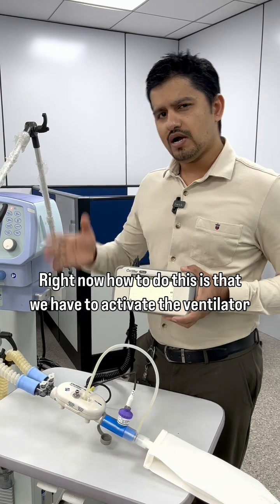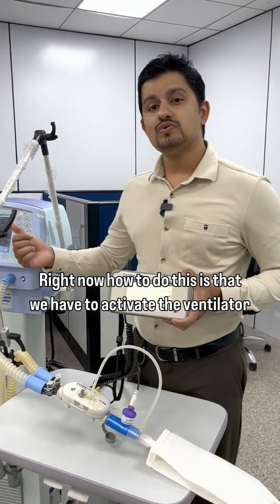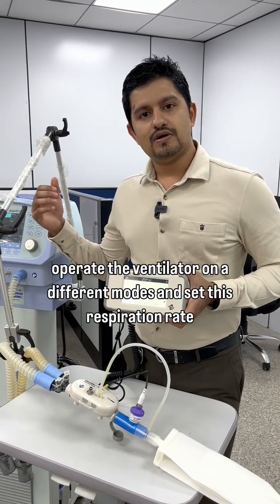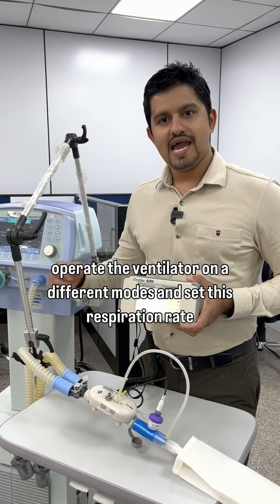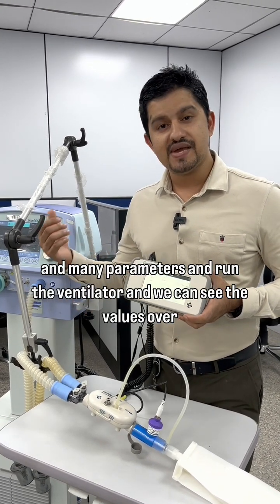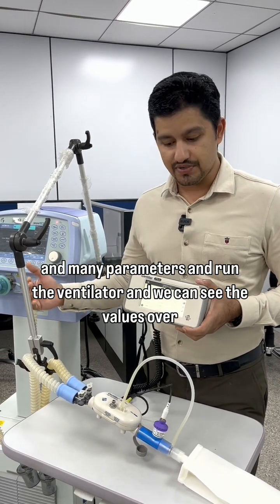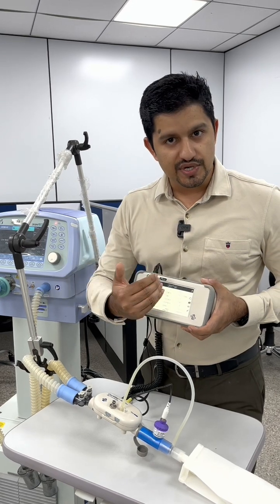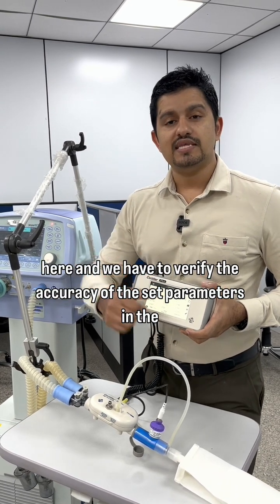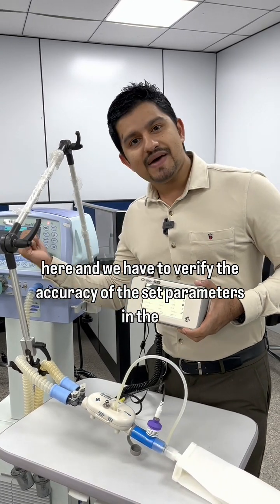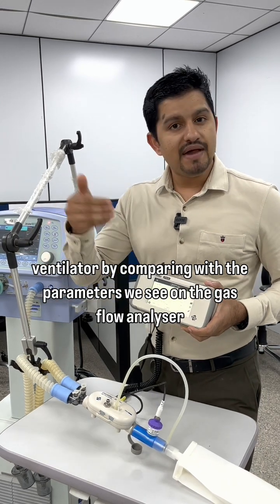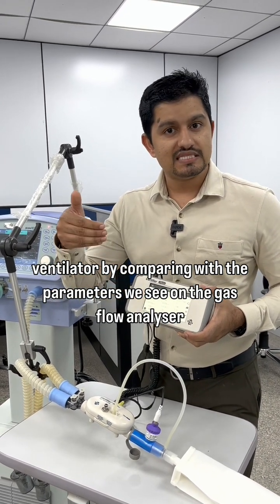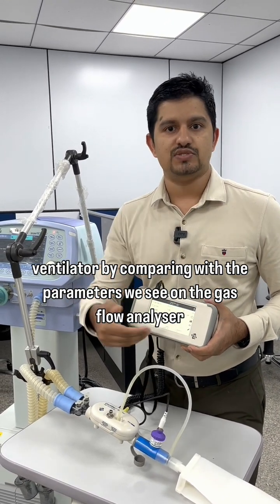Now, how to do this is that we have to activate the ventilator, operate it in different modes, set the respiration rate and many parameters, and run the ventilator. And we can see the values over here. We have to verify the accuracy of the parameters set in the ventilator by comparing them with the parameters we see on the gas flow analyzer.